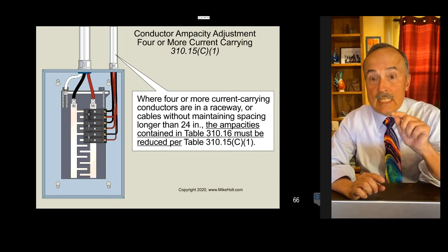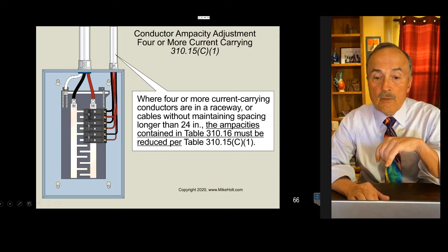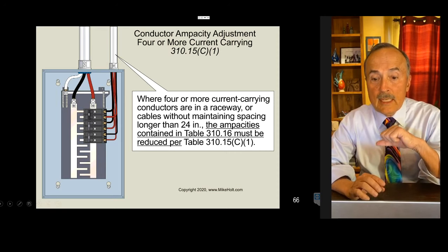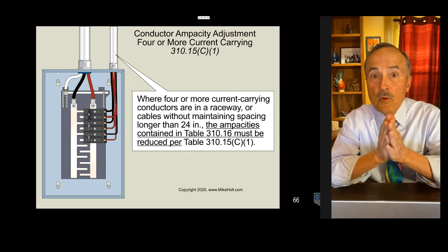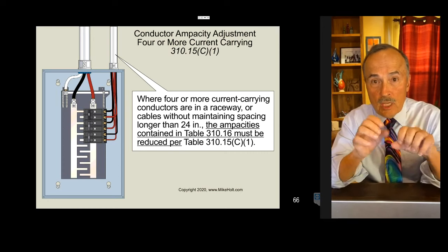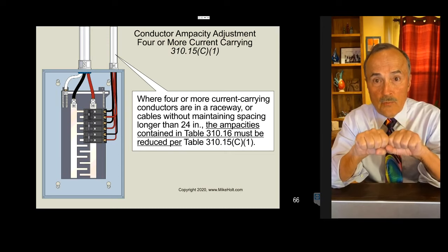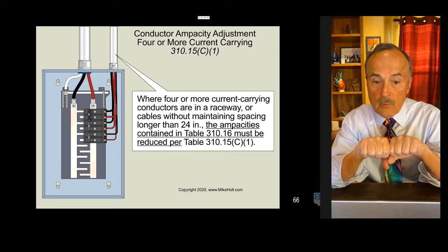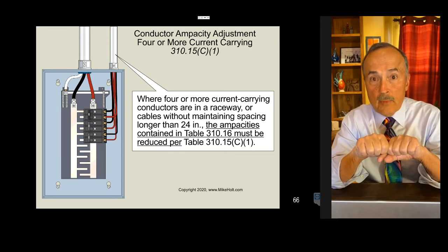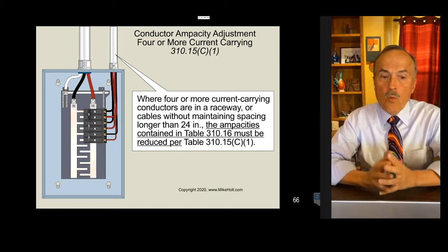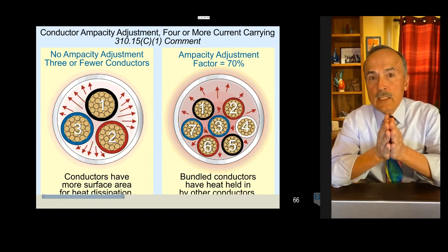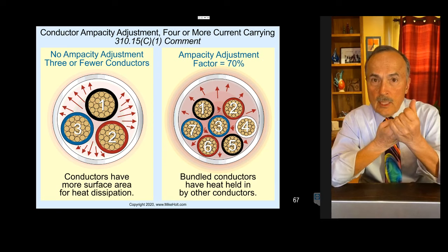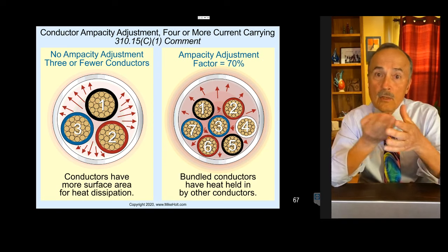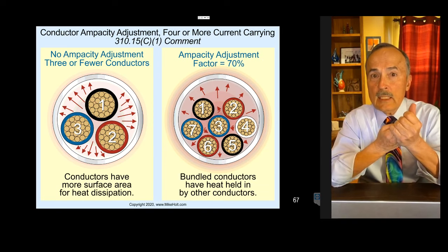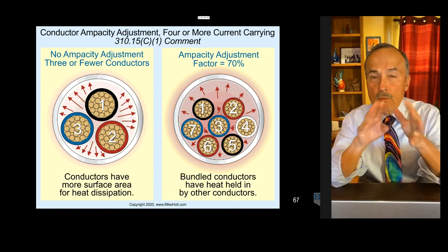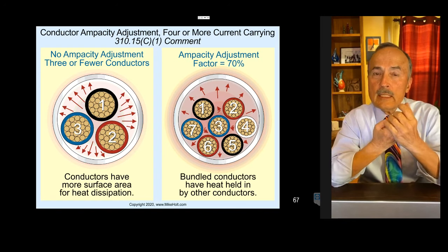So first of all, let's understand that. You have to have not maintained spacing for 24 inches or more. The ampacity contained in Table 310.16, which used to be 310.15(B)(16), must be reduced per Table 310.15(C)(1). So there's a table on the number of conductors that you're going to be bundling together that's going to be 24 inches or more, or rather more than 24, longer than 24 inches. Then you're going to have to adjust the ampacity.